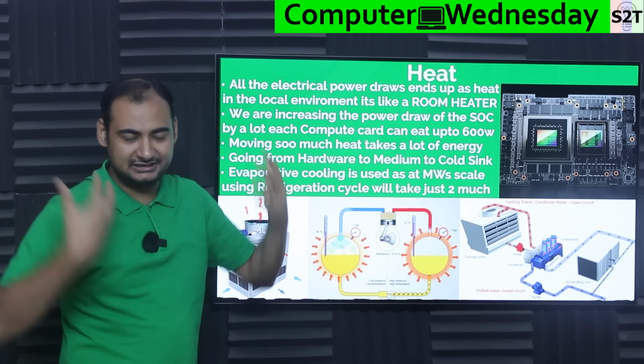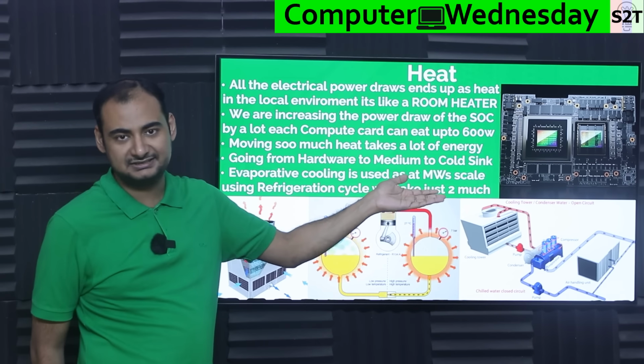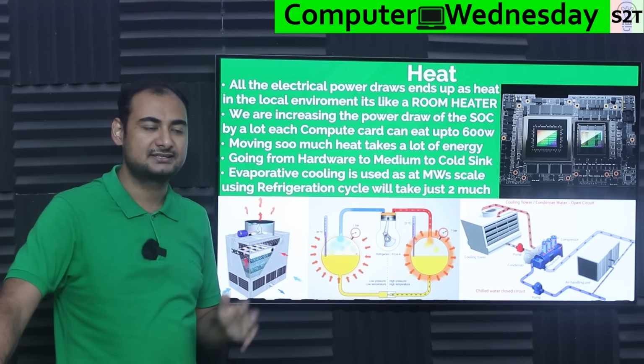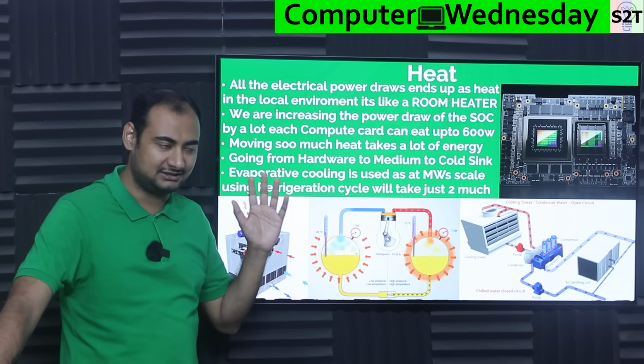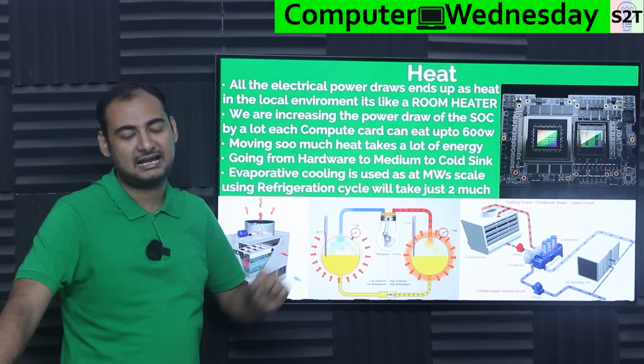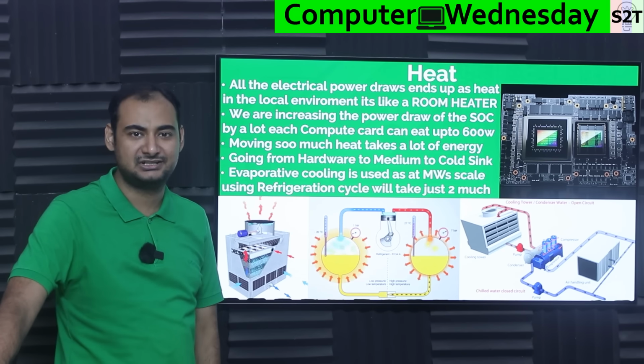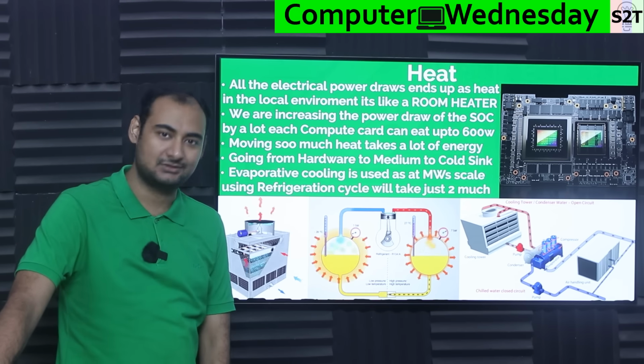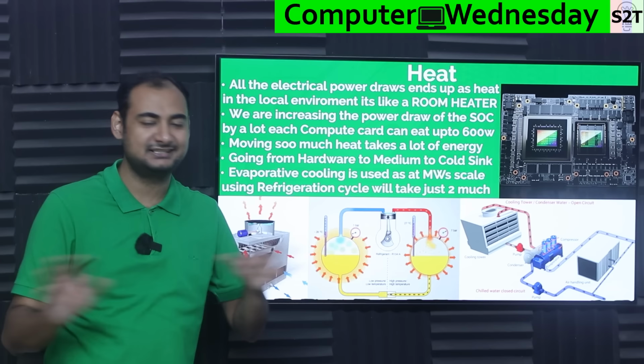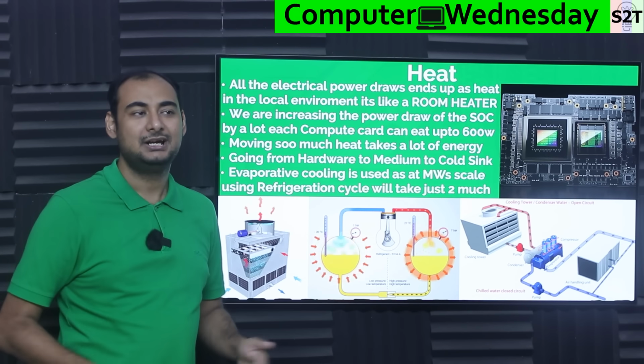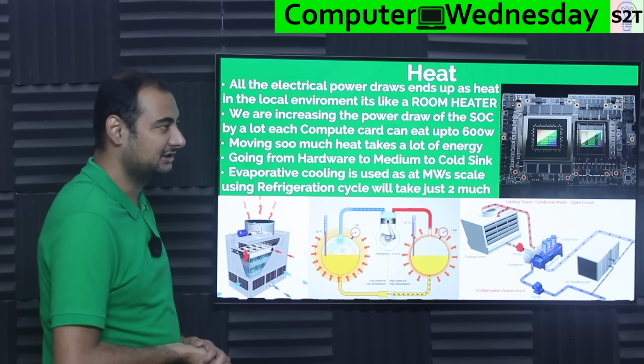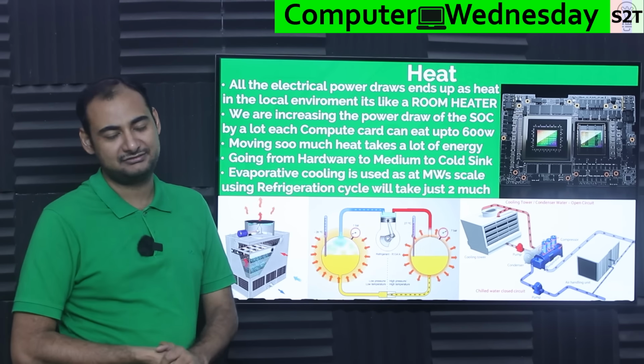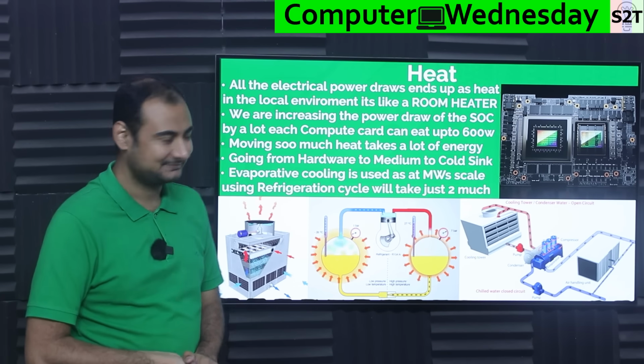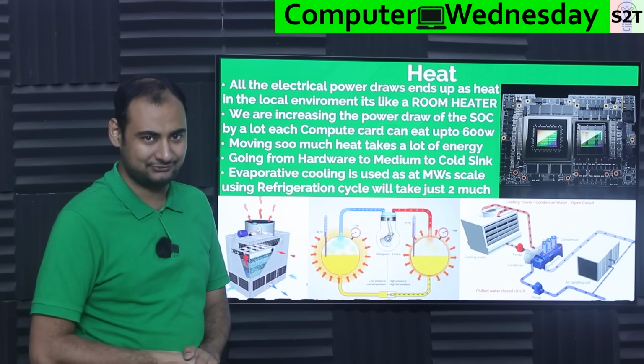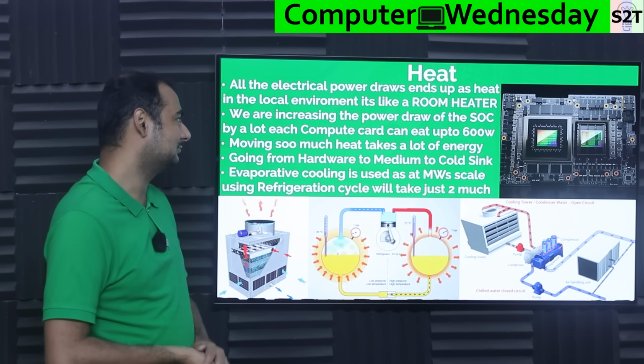If you are dealing with a thermal engineer who is scaling the system, all they will ask is what is your PSU requirement? If you say my per-rack PSU requirement is 200 kilowatts, they're like, okay, that's a 200 kilowatt heater, the end. There is nothing after that. They'll also add some buffer and say, I'm gonna assume this is a 250 kilowatt heater, a powerful room heater. So that's the whole point.